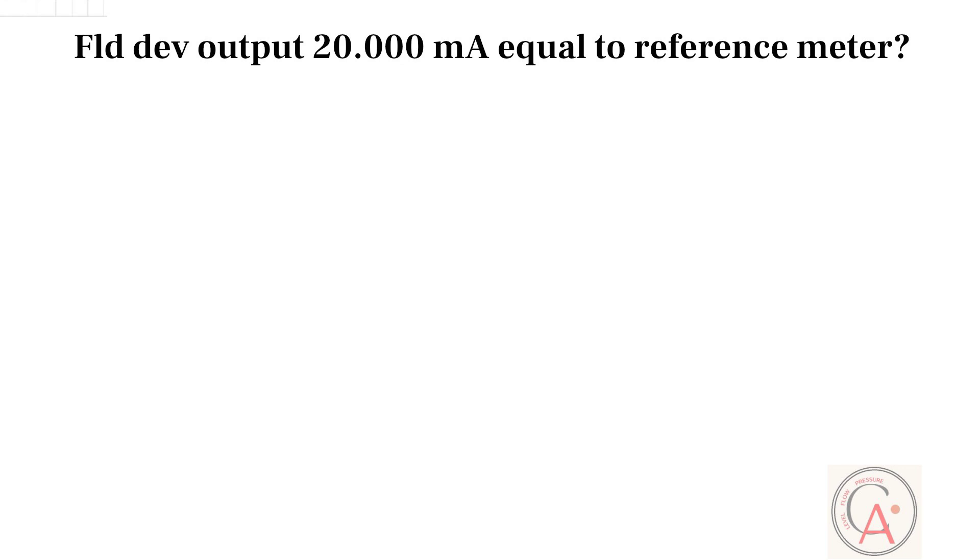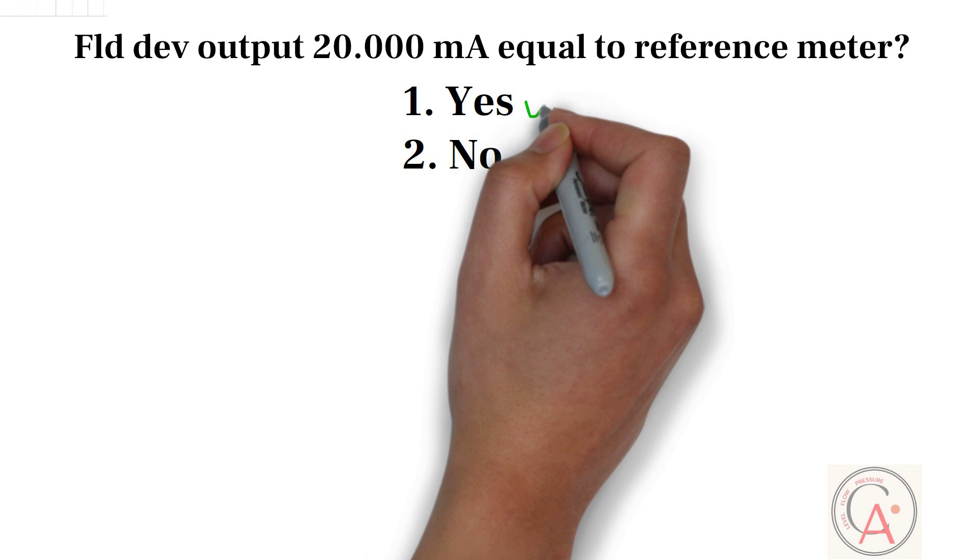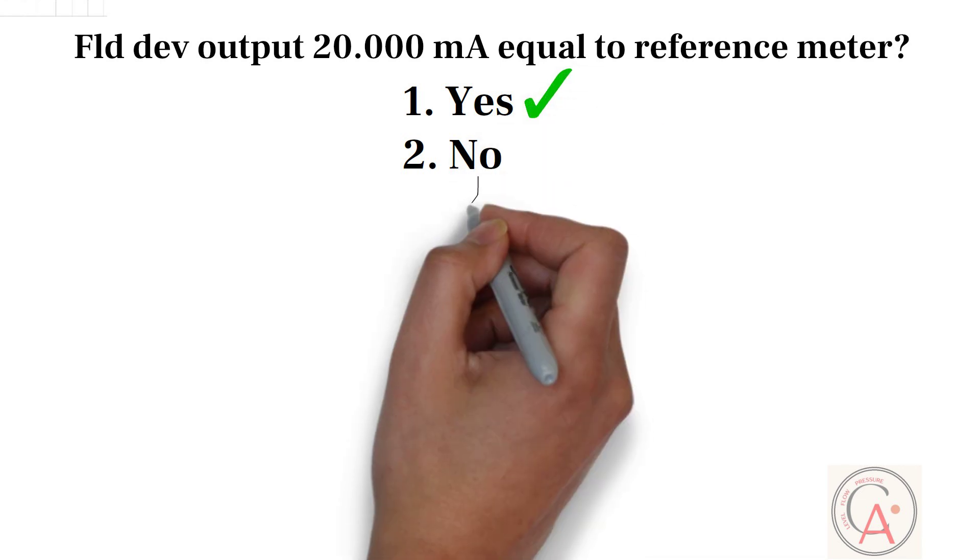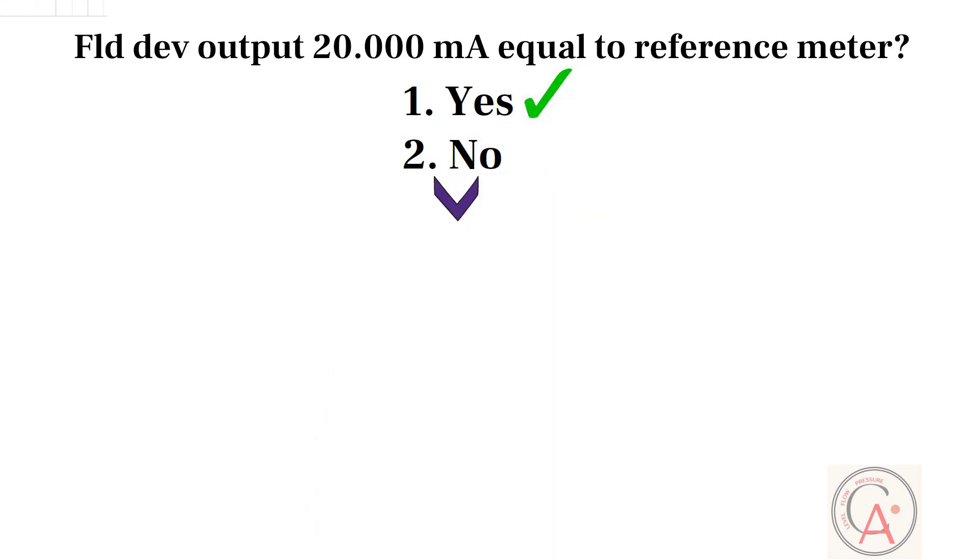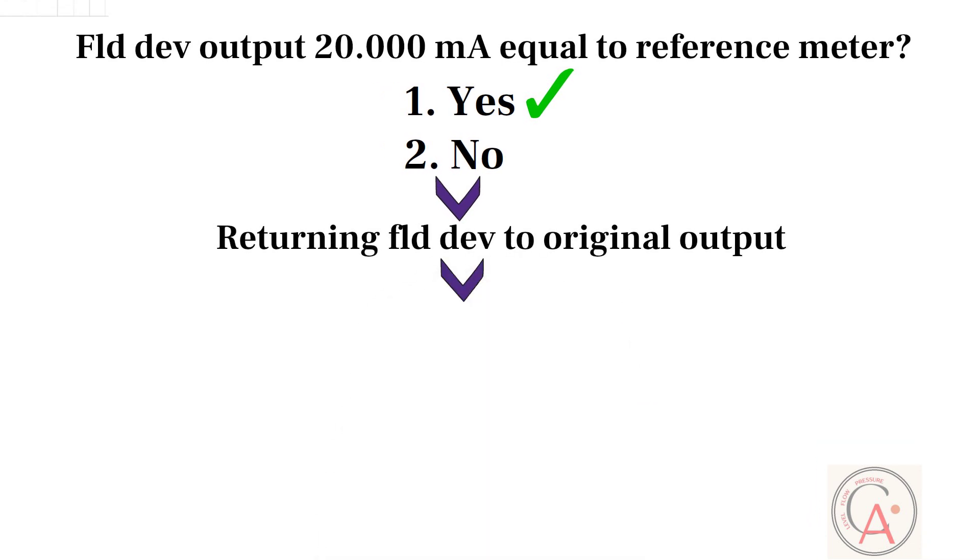Field device output 20 milliampere equal to reference meter message will appear on the screen. Select YES option and press ENTER button. After this, returning field device to original output message appears on the screen. Press ENTER button at this time. Then loop may be returned to automatic control message appears on the screen. At this time, press ENTER button to put loop into automatic control.